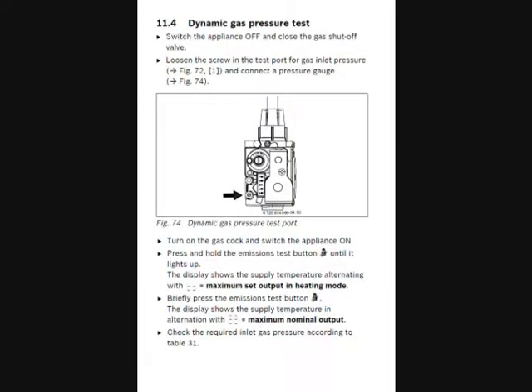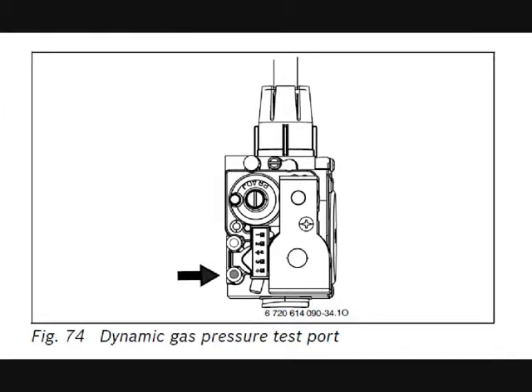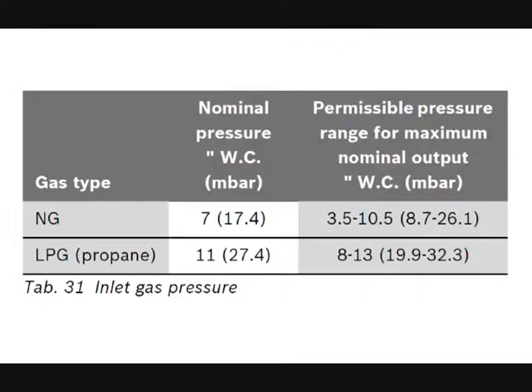It is always wise to verify that your inlet gas pressure is within tolerances before beginning to tune combustion. Follow the few brief steps in section 11.4 on page 78 of the install manual. Check the incoming gas pressure using a manometer in the inlet pressure port shown in Figure 74. For natural gas, the inlet pressure should be around 7 inches of water column. For LP, inlet pressure should be around 11 inches of water column. Table 31 on page 78 also shows the permissible pressure ranges for each type of gas.